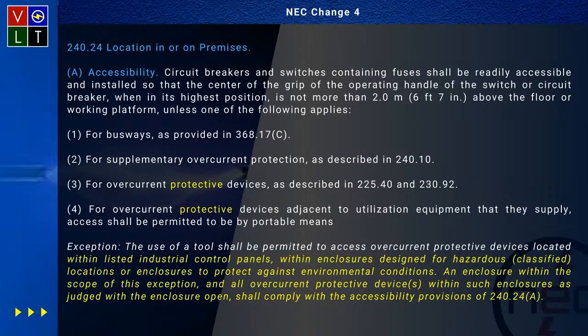They're talking about industrial control panels within enclosures designed for hazardous classified locations, or enclosures to protect from environmental conditions. Basically, these things are completely shut, with little screws all the way around them. You're not really getting into those without using a tool to gain access. That's an exception to permit this.